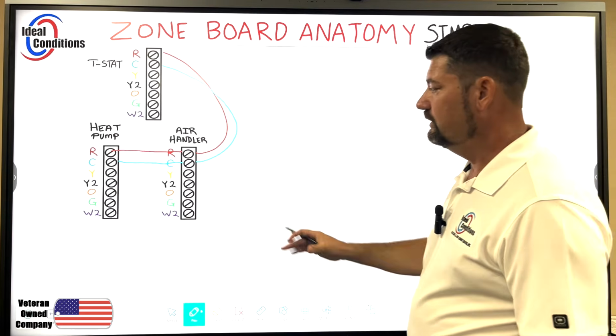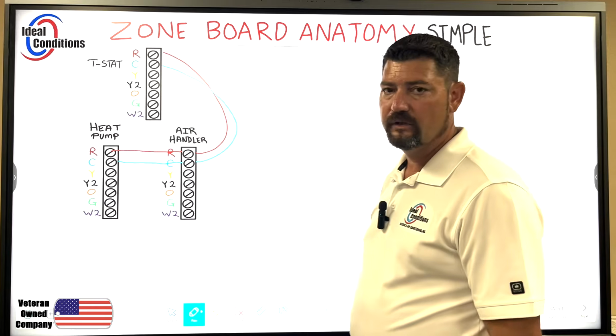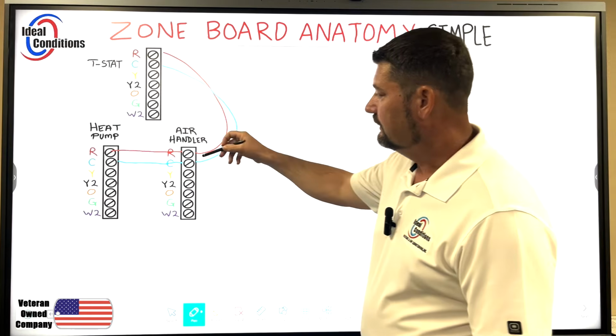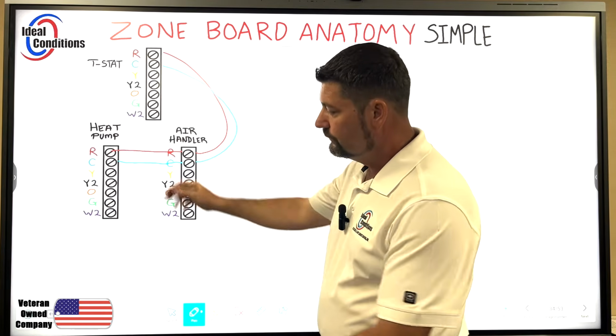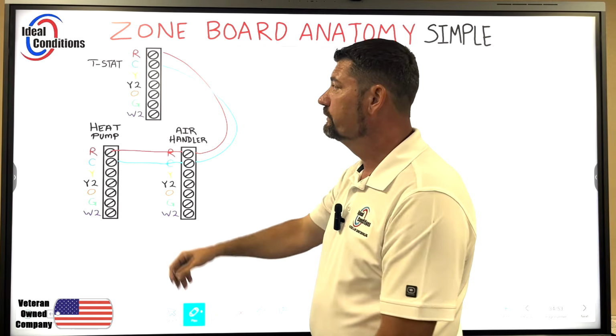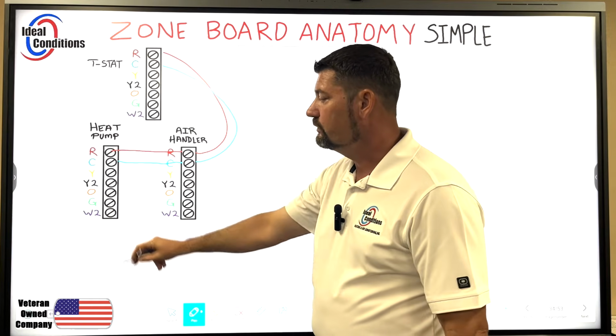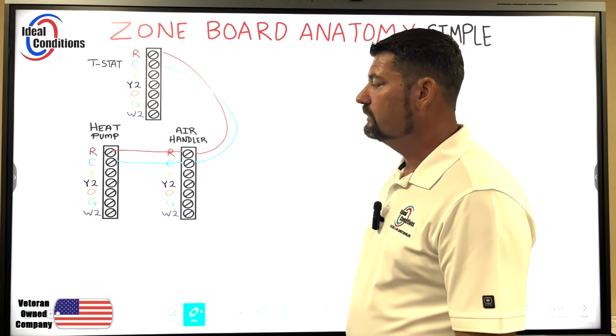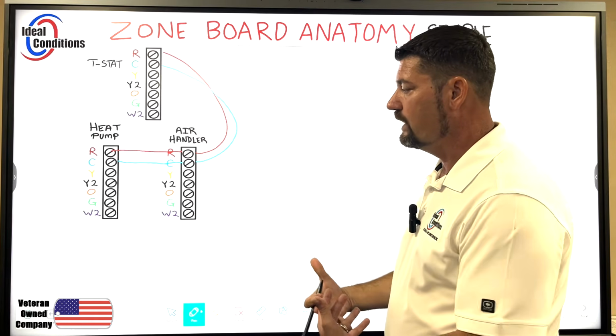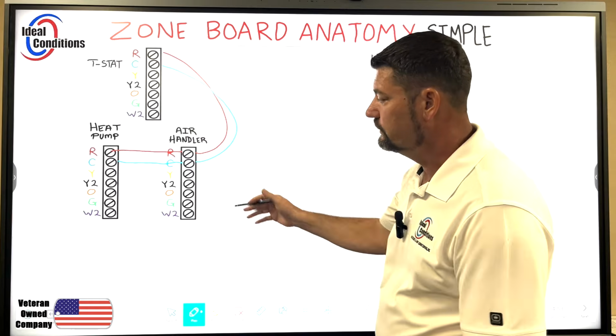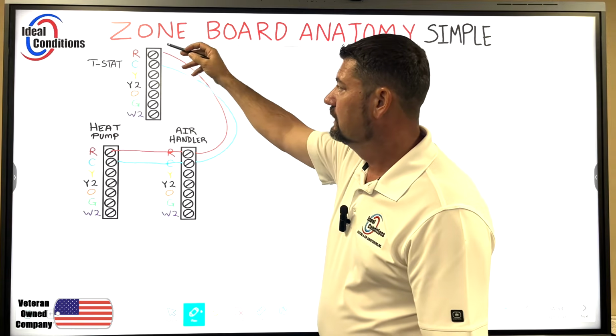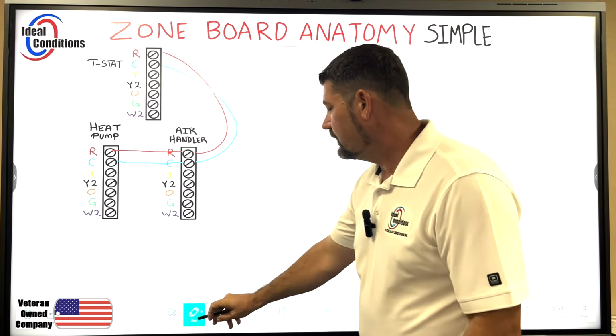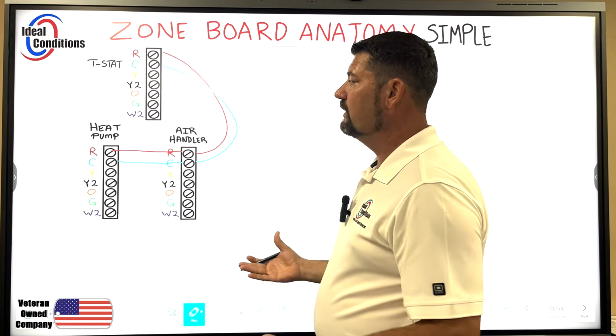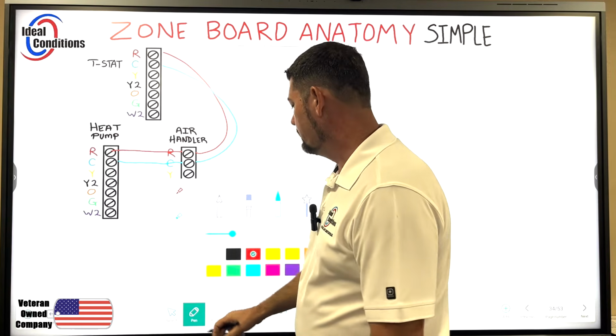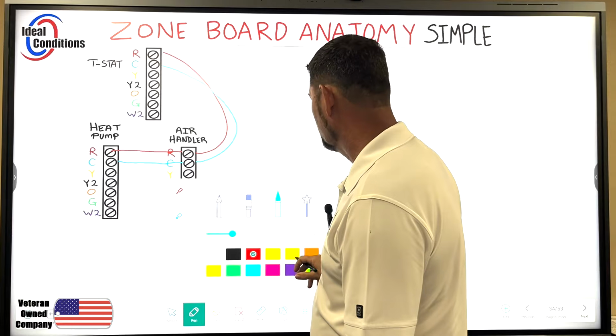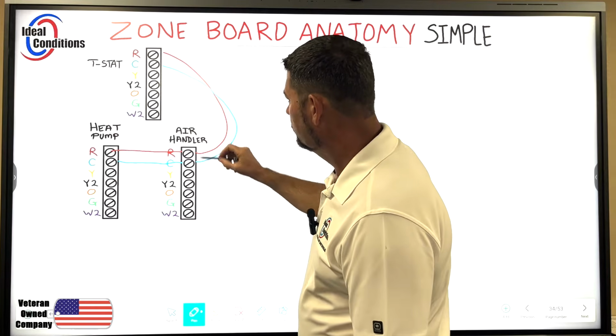And so the unit transformer, which is known as the primary transformer, is now wired to what would be the defrost control board. And that's what this block would represent. And this would be the air handler block for all your wires that converge inside the air handler if you were to just pigtail everything in there. There's nothing complicated. You typically wire your systems all day, every day, in this manner. I'm just going to switch the color up, and it's just wire for wire.